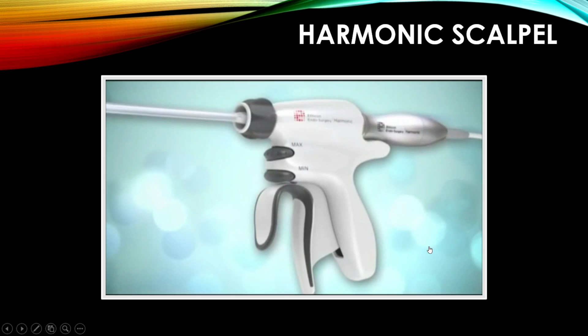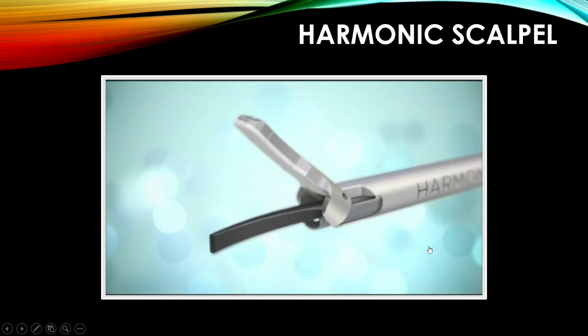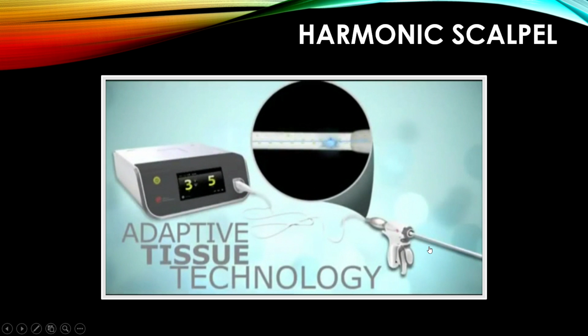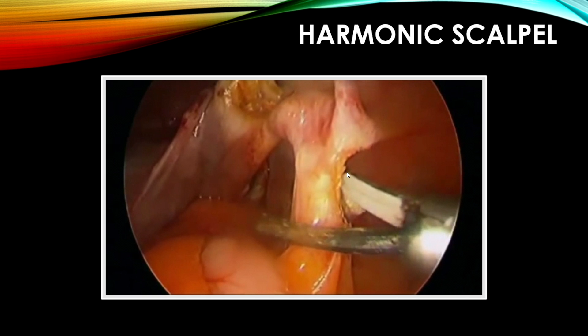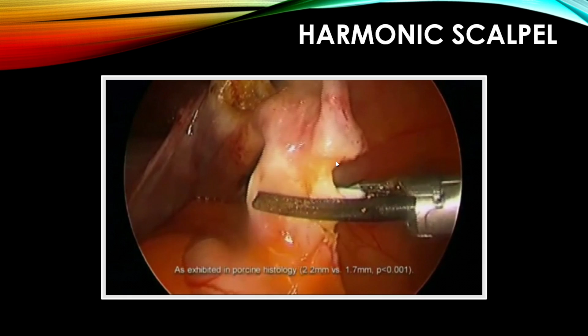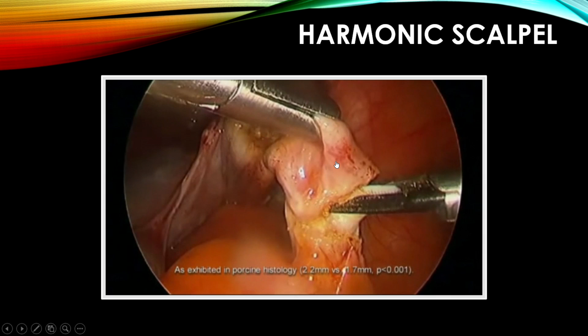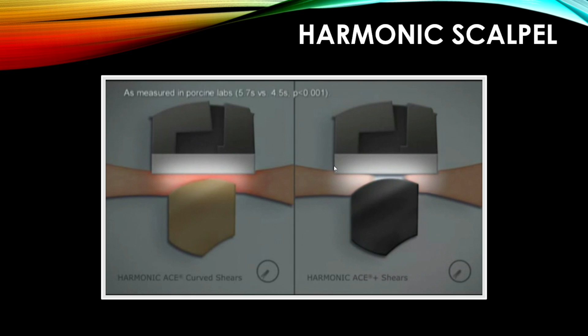It has two types of setting, 3 to 5, and minimum can be 1 also. 1 means 15,000 vibrations, 2 means 25, 3 means 35, 4 means 45 and 5 means 55. It has an adaptive tissue technology. By default it is 3 and 5 setting, 3 means 35. So, suppose you have to coagulate and tissue is vascular, you will press the minimum. In minimum, coagulation is more, cutting is delayed, and if tissue is avascular you will press maximum. In maximum, coagulation is less, cutting is fast, and this way you can control.